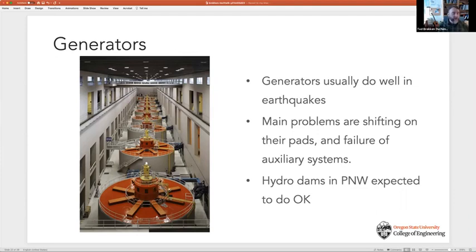These are actually pretty robust to shaking. They're not often directly damaged by the shaking, but they can shift on their pads, so the foundations can get shifted and cause misalignment problems. Also, any auxiliary systems supporting them can be damaged as well. For the most part, though, we expect generators to do pretty well in a Cascadia Subduction Zone earthquake—there will be some outages, but they're most likely not the most vulnerable component of the system.